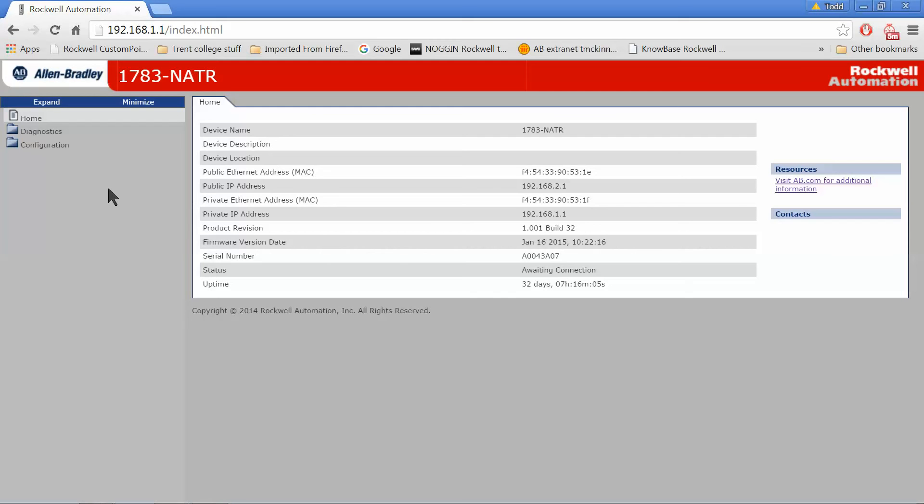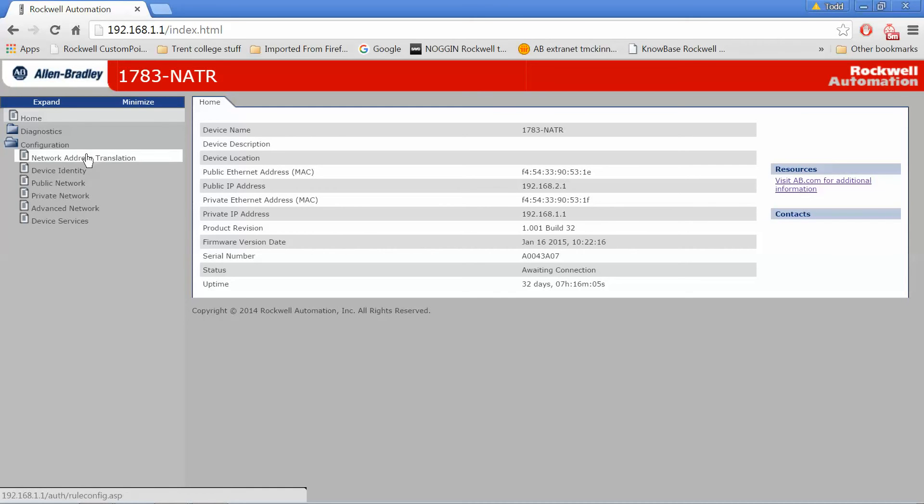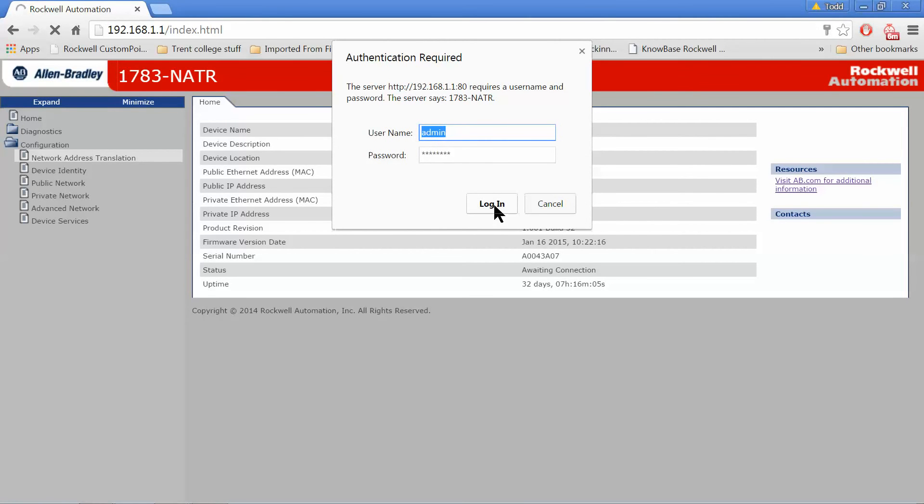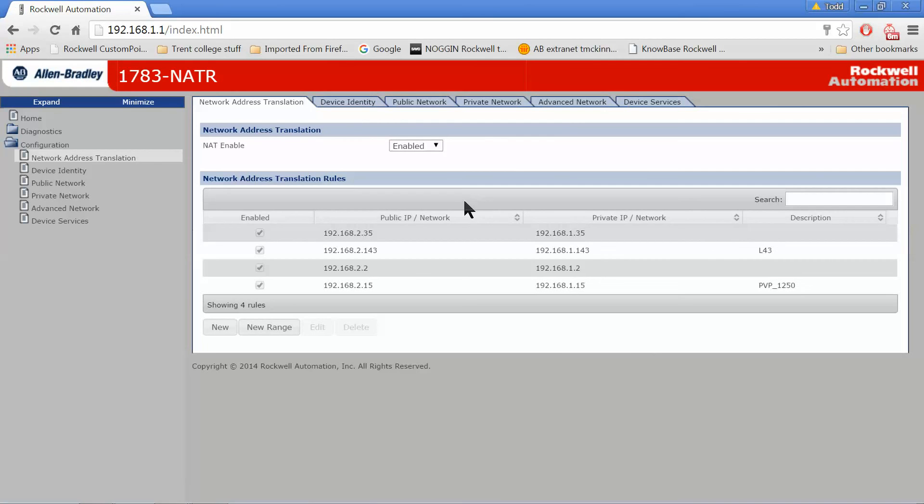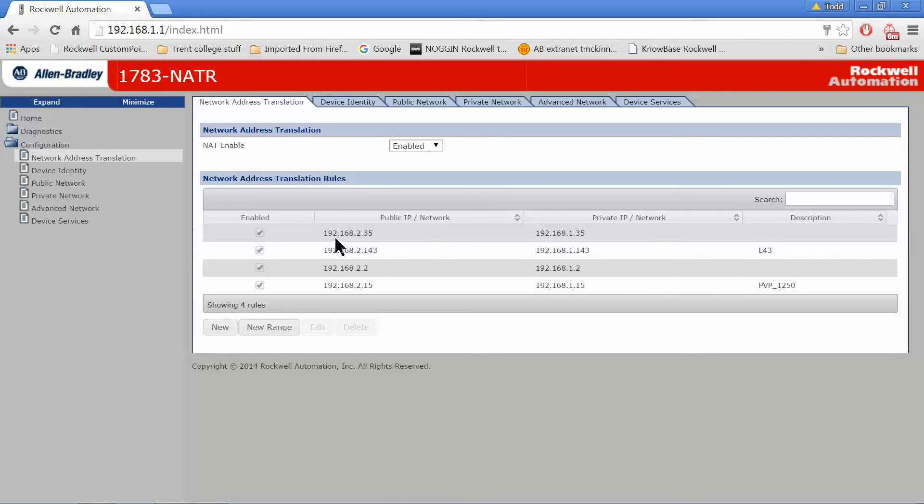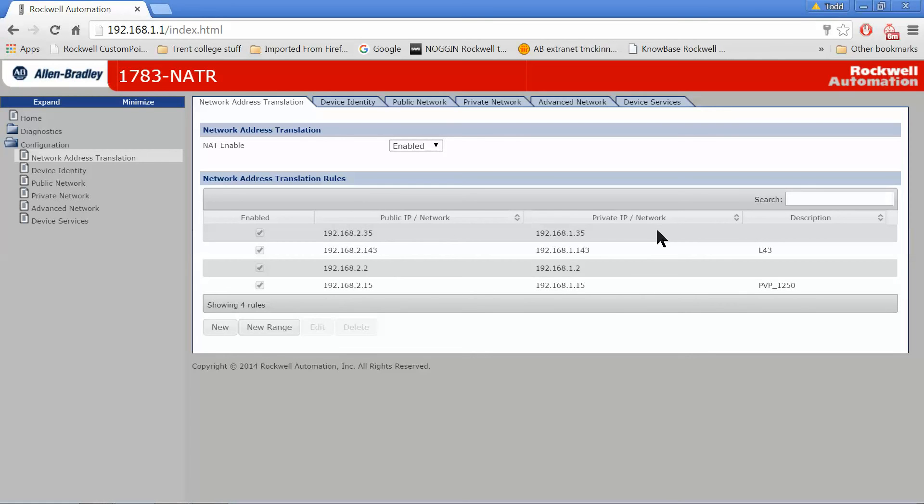Now once we're in the webpage, let's go to the configuration tab and this is where we set up our network address translation tables. There's where my admin and my password comes in. I had already set up a couple of different NAT routes for my device. In my case, I have my public IP address subnet as 192.168.2. This is going to be whatever your office or plant network subnet is. And then the private IP address. These are the IP addresses of my CompactLogix, PowerFlex drives, PanelView Pluses, whatever you want them to be. They could be computers for that matter.